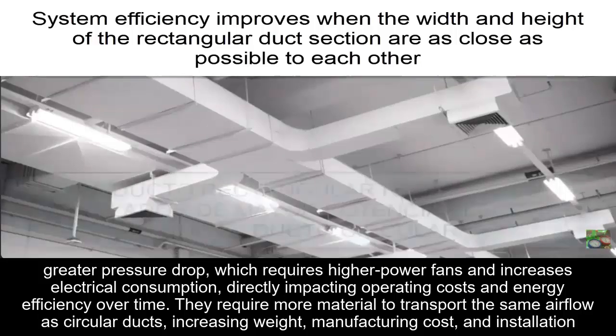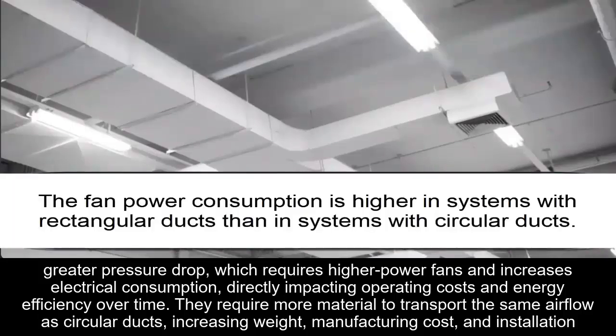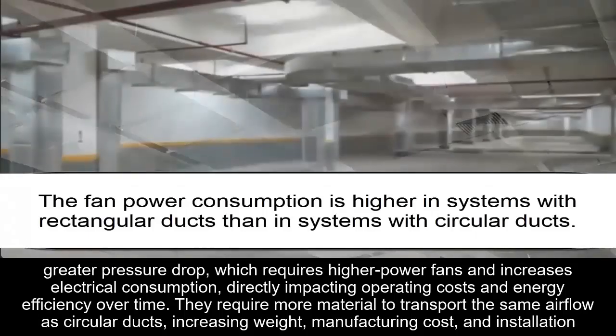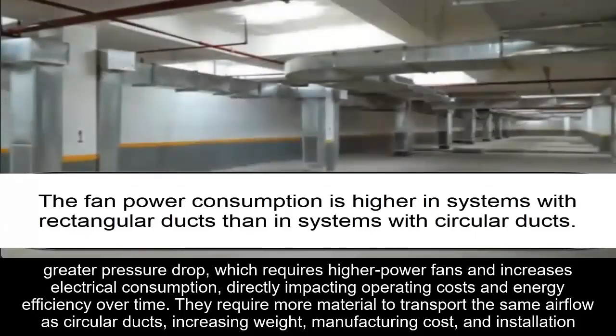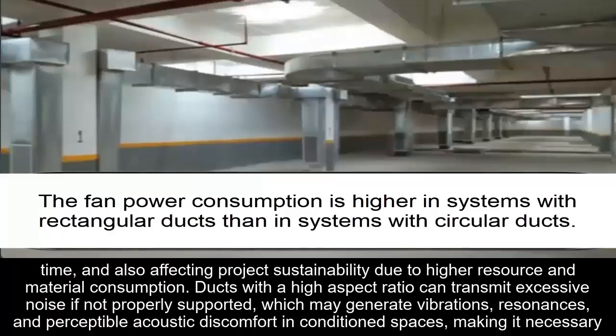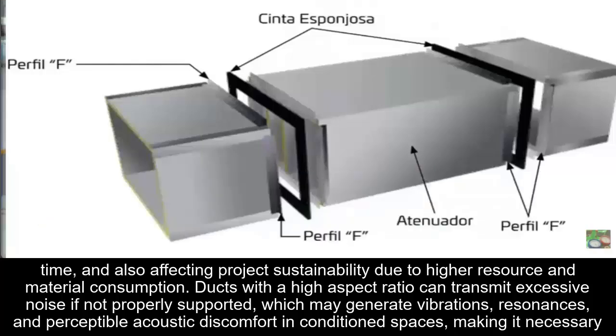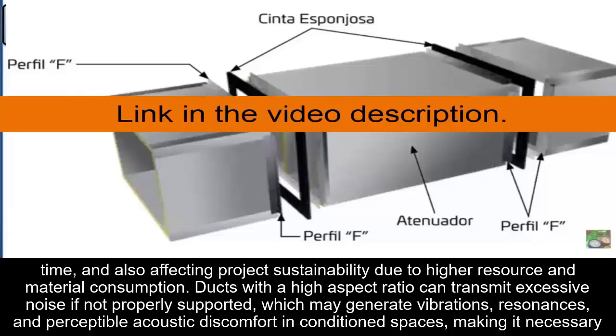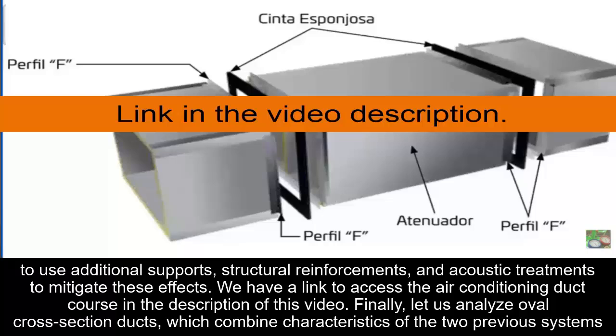They require more material to transport the same airflow as circular ducts, increasing weight, manufacturing cost, and installation time, and also affecting project sustainability due to higher resources and material consumption. Ducts with a high aspect ratio can transmit excessive noise if not properly supported, which may generate vibrations, resonances, and acoustic discomfort in conditioned spaces, making it necessary to use additional supports, structural reinforcements, and acoustic treatments to mitigate these effects.